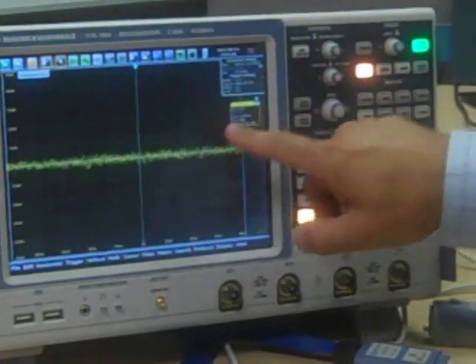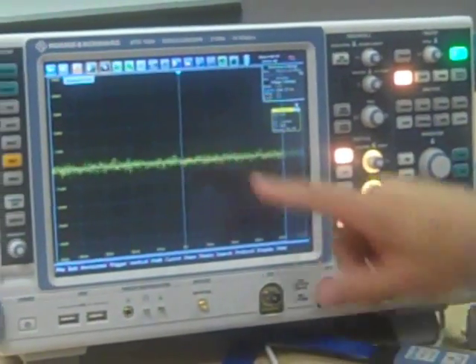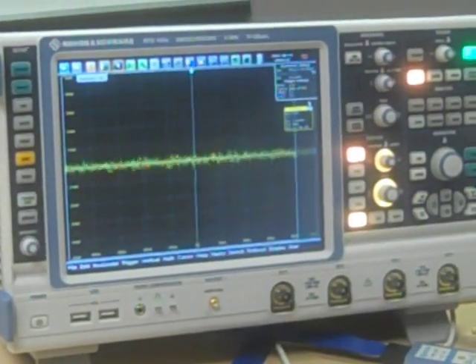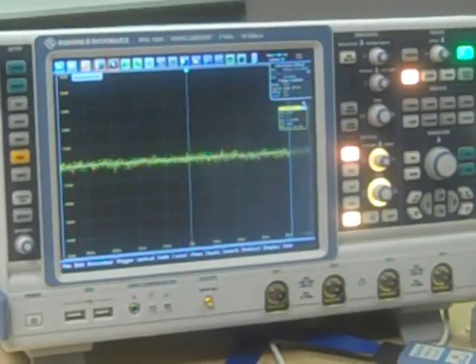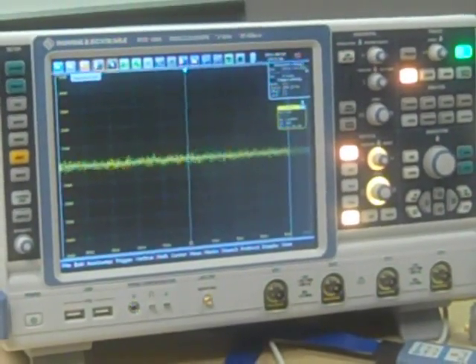Let's go ahead and look at the waveform here. We see the noise level. This is one millivolt per division. Now on most scopes, that's not a gain stage, but rather is a zoom feature. In this scope, it's actually a gain stage.